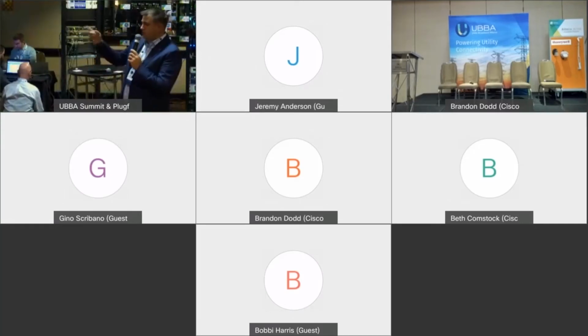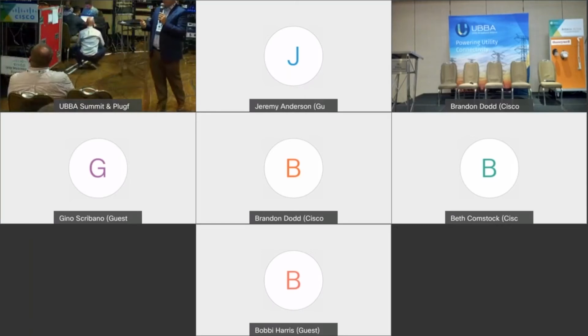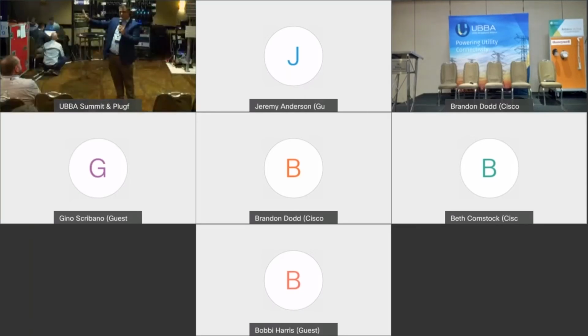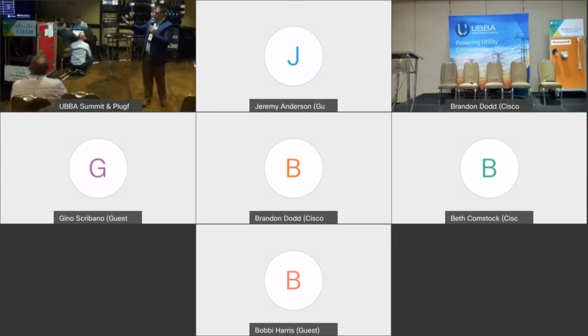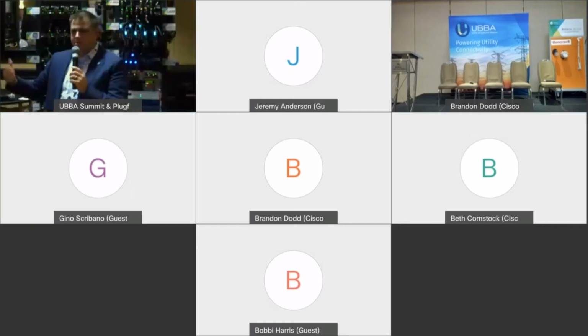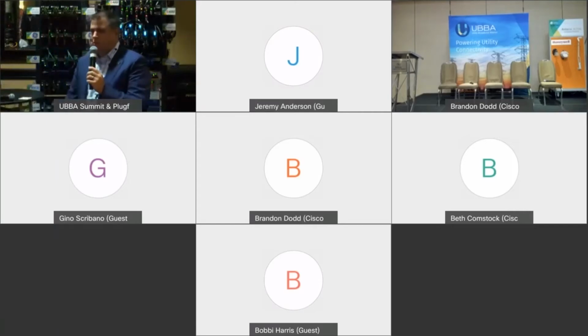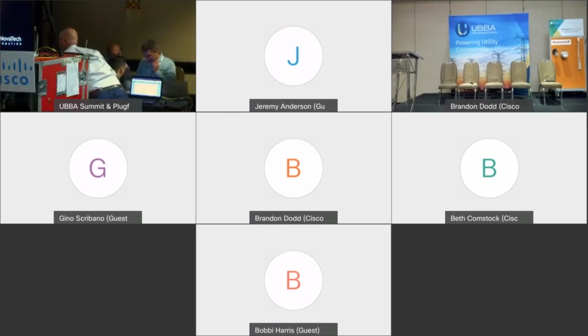In this case, the two bottom devices are having to effectively reboot their modem. They don't reboot the entire device and reload their profile to go to US Cellular and AT&T, connect to their public network. Beyond that, we have to reestablish any security that we're doing, so IPsec or other things like that. What we're showing here is DNP traffic. This is what the master station is seeing. We also have to reinstantiate those DNP sessions. So that can take seconds to minutes. If somebody wants to dig into this deeper, we can go through each of the delays through each of those segments. In the meantime, Mike, who are we calling up to share?